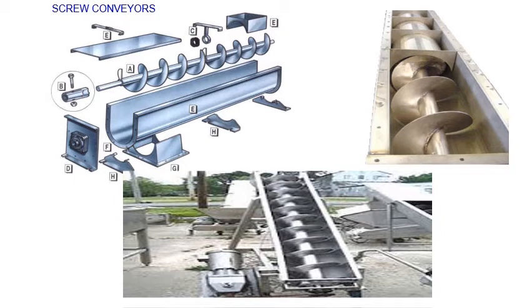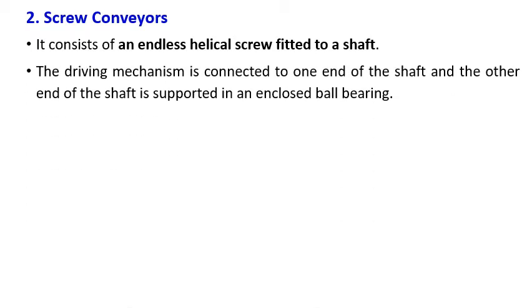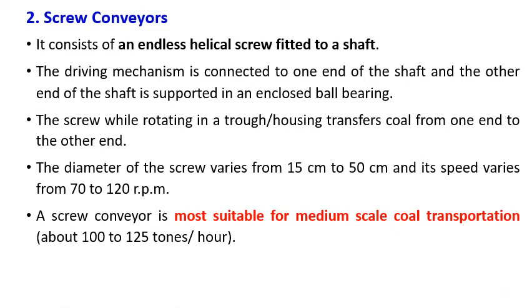The screw conveyor consists of an endless helical screw fitted to a shaft. The driving mechanism is connected to one end of the shaft and the other end is supported in an enclosed ball bearing. The screw, while rotating in the trough housing, transfers material from one end to the other. The diameter of the screw varies from 15 centimeters to 50 centimeters and its speed varies from 70 to 120 RPM. The screw conveyor is most suitable for medium-scale coal transportation, around 100 to 125 tons per hour.